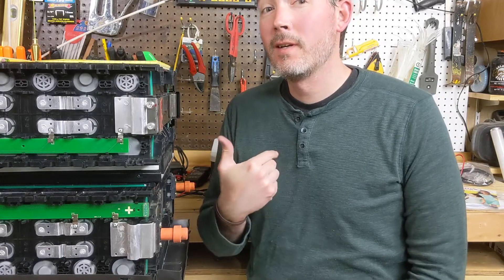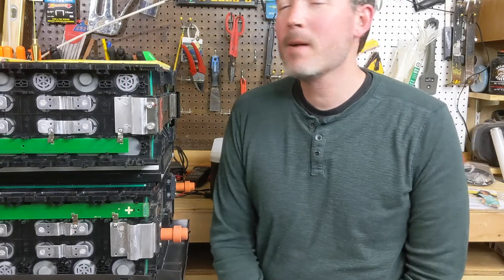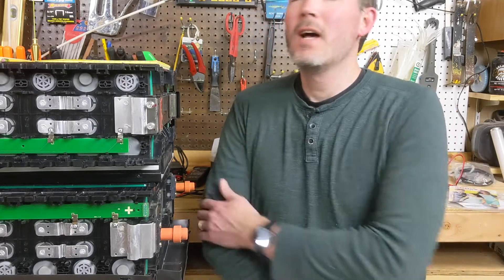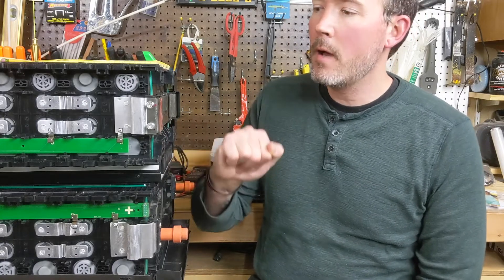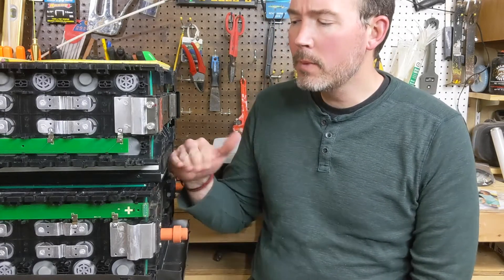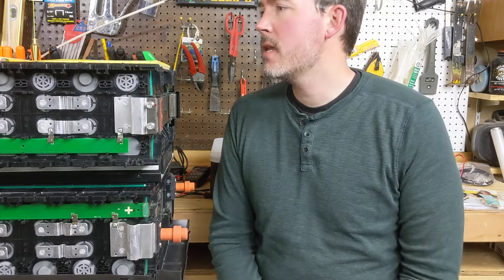So what did the kids learn today? Well first, dad — me — I can only lift 160 pounds once in a day apparently. That's about 73 kilograms. Luckily, taking it down to about 122.6 pounds after removing the heat sinks, I was able to do that again. We also talked about heat sinks a bit further. The heat sinks in these original batteries were used to dissipate a lot of heat — these were used in electric buses, utilizing at their maximum capacity every day, bringing voltage up and down as much as possible. So the heat they were pulling off was really important. I don't think I'll be using those for my application, so I'll probably be removing them, but we'll see after capacity testing.